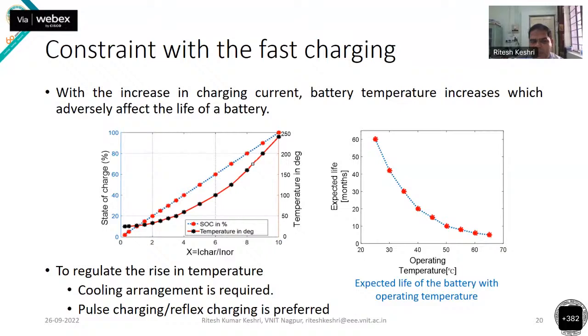So you have to respect the thermal constraint, accounting for temperature effects to ensure a proper charging strategy. For example, if we operate the battery at an average of 50 degrees Celsius through charging and discharging, you will lose the battery in about 12 months. But if you maintain the operating temperature at 40 degrees Celsius, it may last around 22 months, or about 2 years.